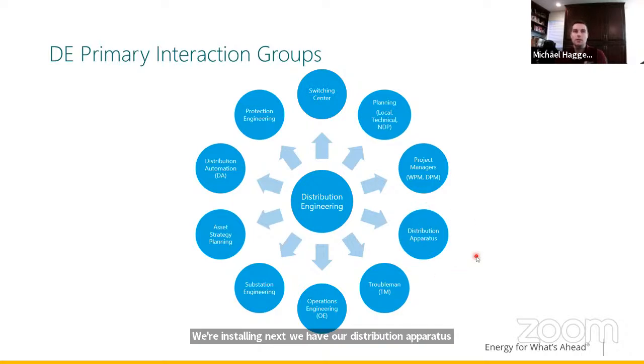They're responsible for field verifying and endpoint testing our apparatus out in the field, like a remote automatic recloser or a remote control switch. Someone has to make sure those devices are working properly and have the right settings, so we work closely with them on that. If there's an error, for example a remote control switch where the switching center sends the close signal and the switch isn't closing, they'll create a trouble ticket that comes through us and gets routed to distribution apparatus to verify whether the device is still needed and has the right settings, then they'll go in and fix it.